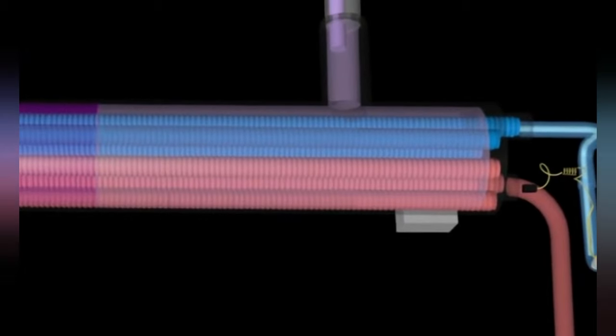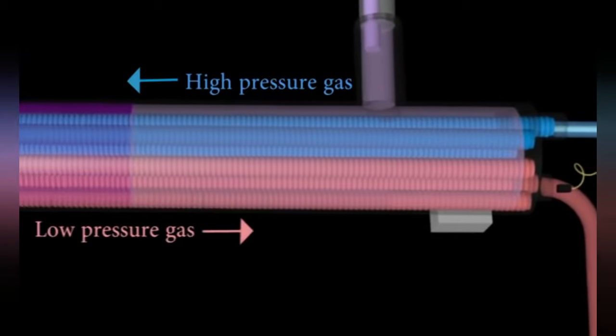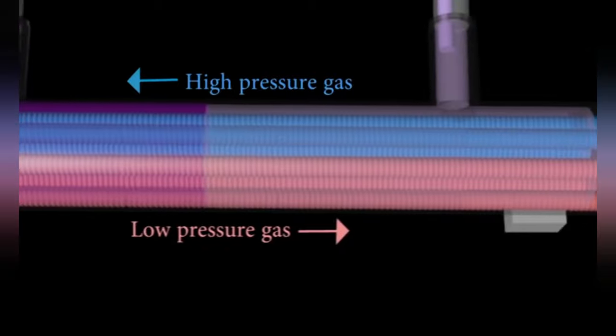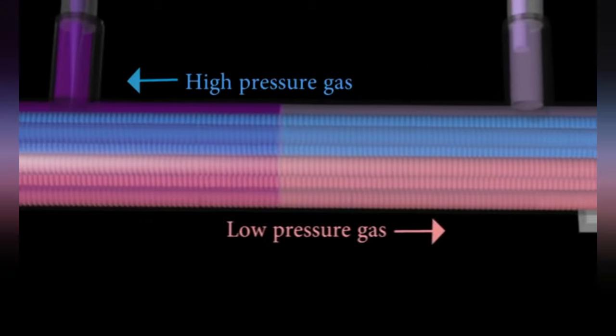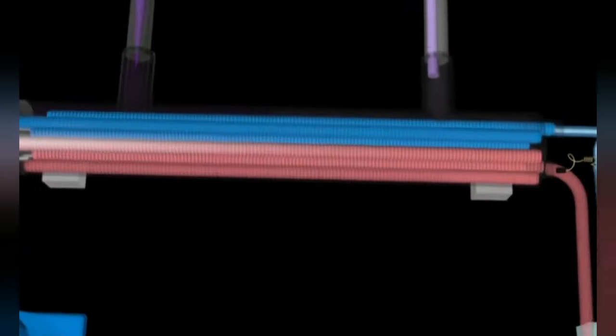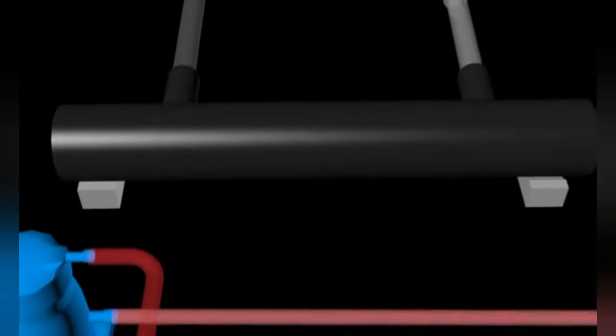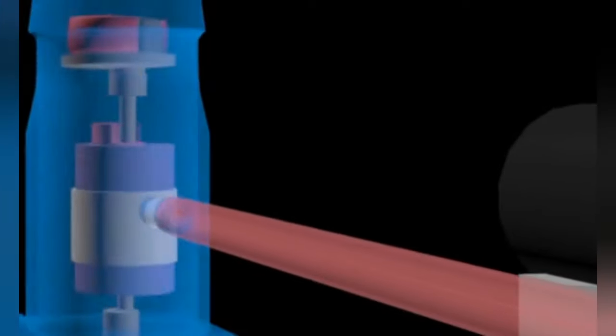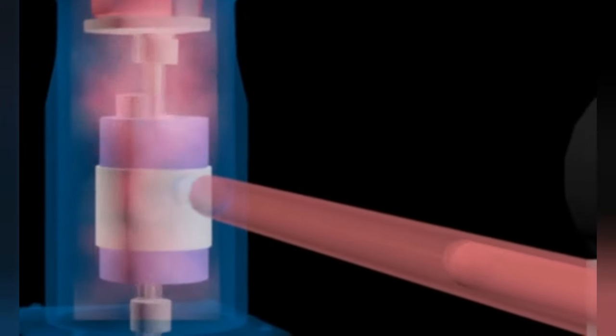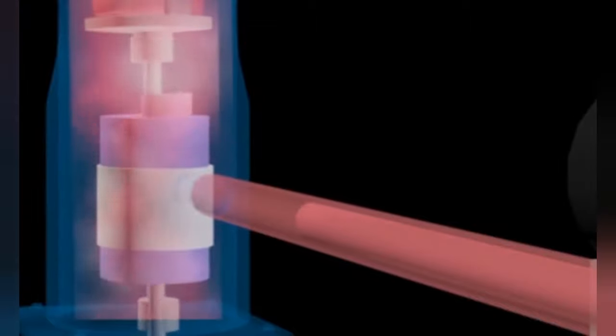The most commonly used evaporator is the shell and tube type, where the refrigerant flows in the tube and water floods the shell. The evaporator is insulated to reduce heat transfer. The refrigerant in low pressure gas then returns to the compressor to continue the next cycle.